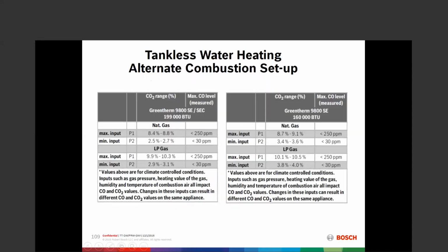So if for whatever reason you don't trust our combustion auto adjust, it seems like too much witchcraft or something, you absolutely can use your analyzer, and we give you the table where you can manually force high fire and manually force low fire, and go through all of these steps manually and set it up with a combustion analyzer. If you want to do that, you can do that.